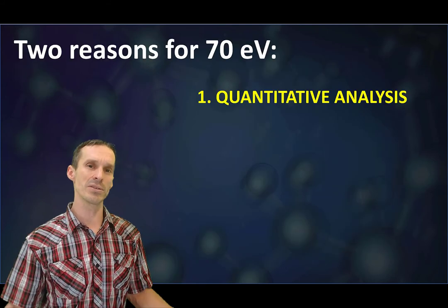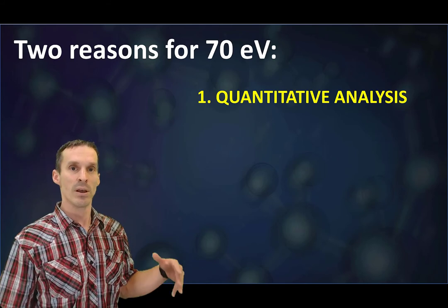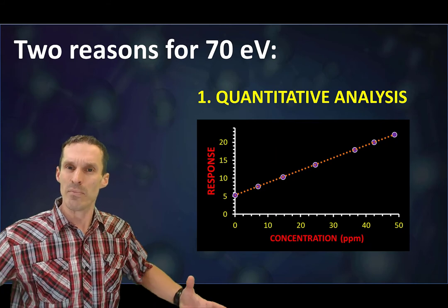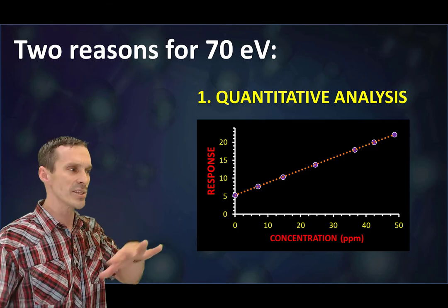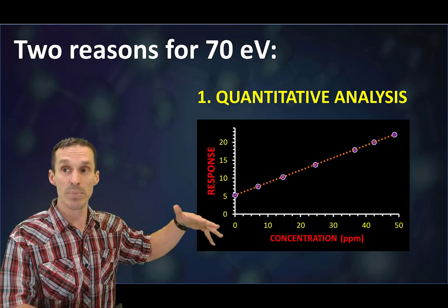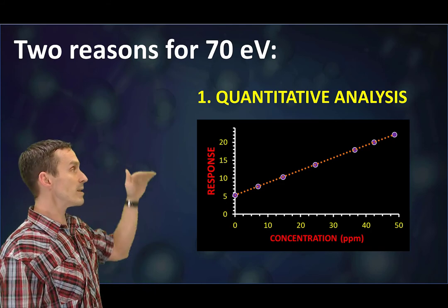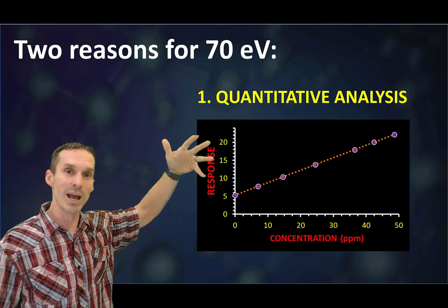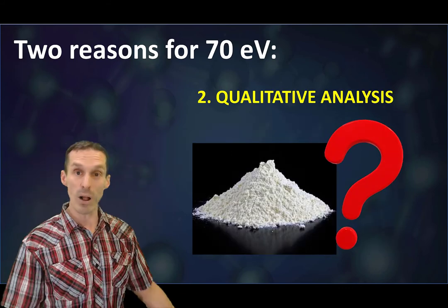To really get down to it, there are two reasons that we want to pick that specific voltage. One is for quantitative analysis. Not only do we want to get the most ionization that we can get, but we want it to be consistent as well. We don't want the sample signals to change because of our mass spectrometer. We want it to change with concentration. By picking 70 electron volts, things are pretty stable at that range. It's a nice plateau on the top of the curve.